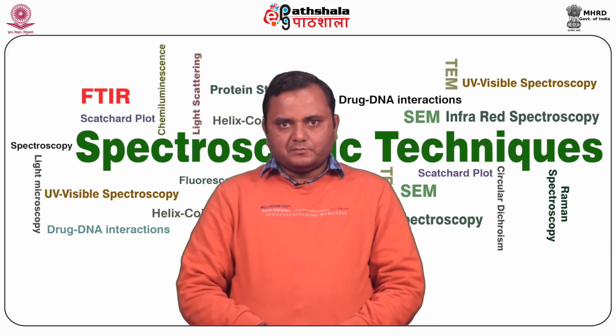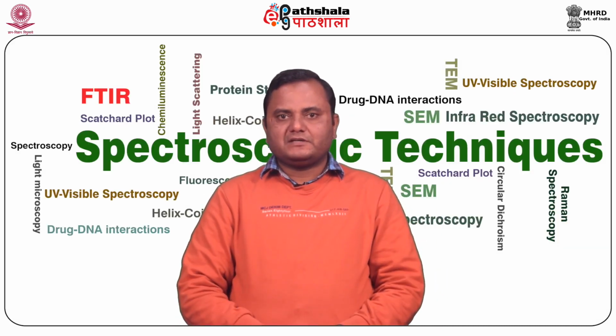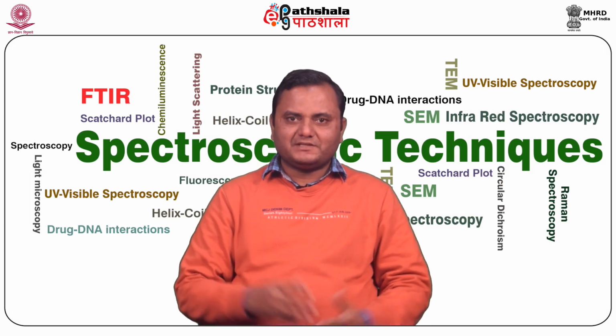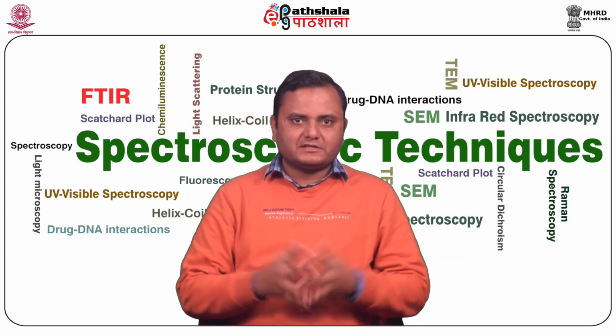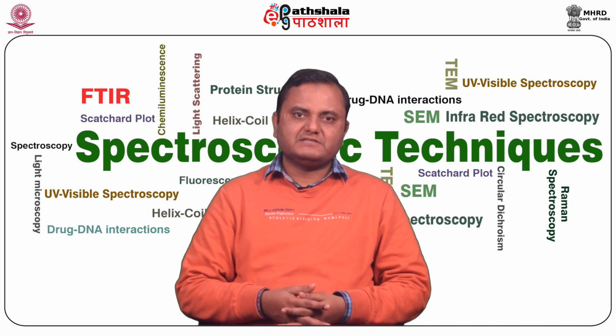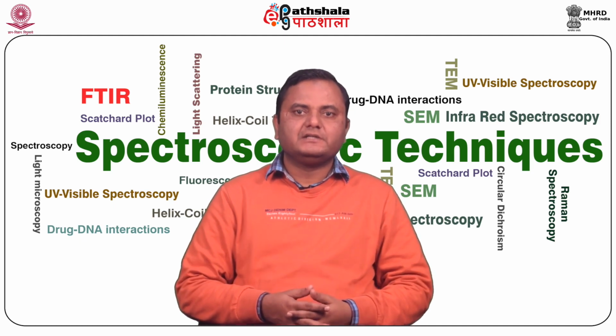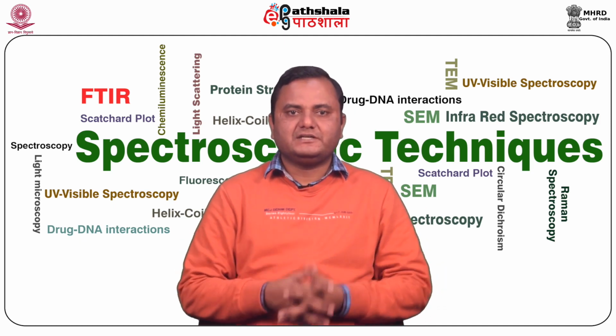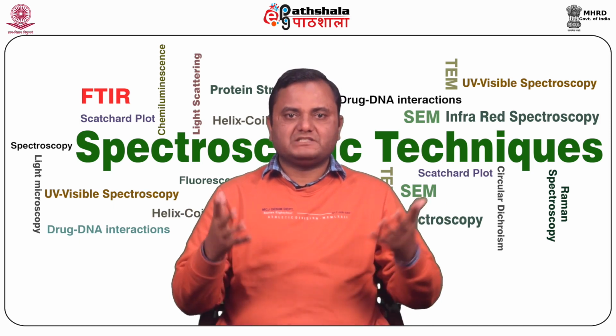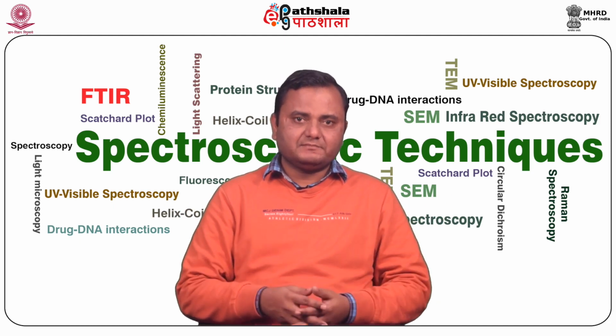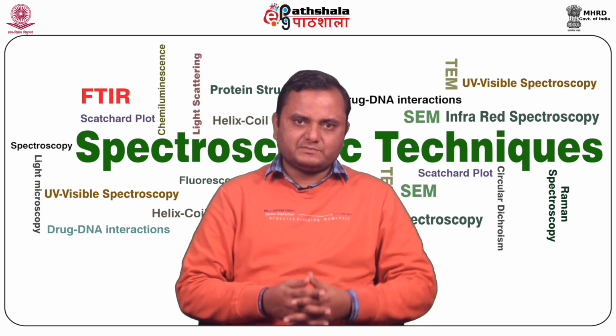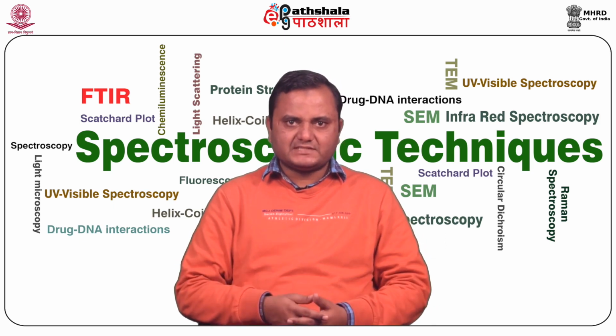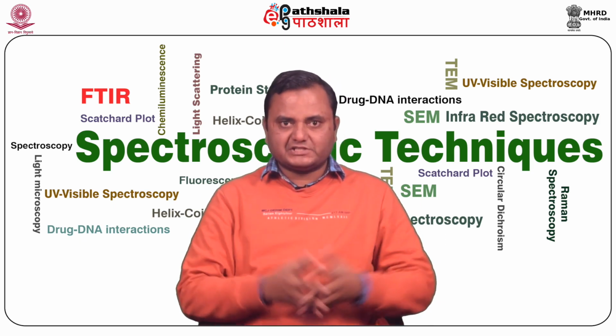The other important component, although it's not part of the spectrofluorometer but it is used for the study, is the cuvette. It should be a fluorescence cuvette, a special type of cuvette, and it has four transparent sides. It is generally made of quartz, but may be of glass, but a quartz cuvette is preferred because of its very low absorbance and other advanced features.